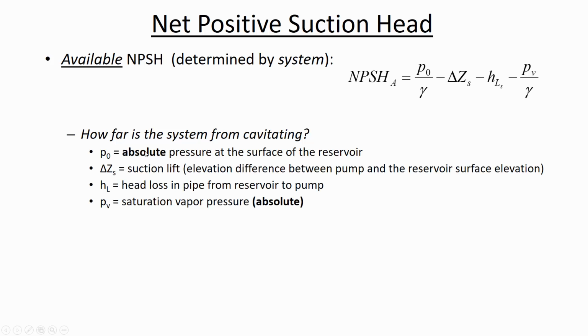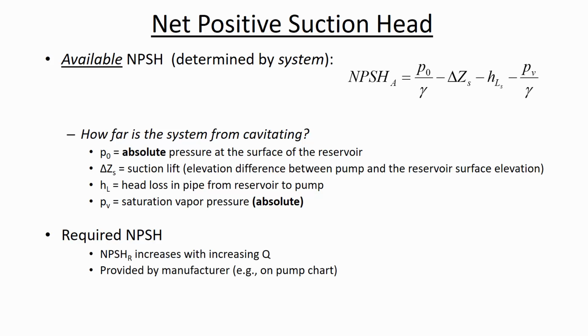So here are the definitions for each of those terms. One thing I'll point out is that we're going to be measuring pressure and vapor pressure in absolute terms. And so for atmospheric pressure, we wouldn't put 0 here for the P naught. We'd put, if it's at sea level, 101,325 pascals for the atmospheric pressure. Now, we're comparing available and required. The required suction head is defined by the pump manufacturer. The idea, though, is that how much is required increases as the flow rate goes up.